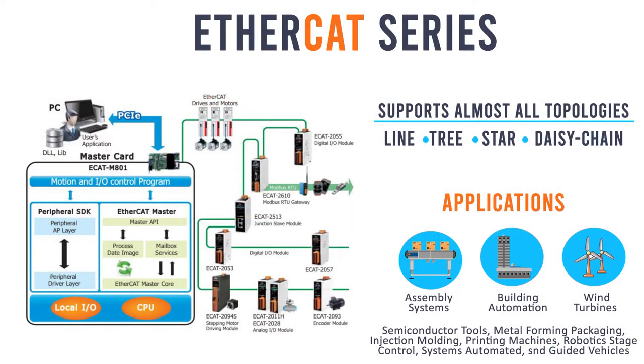Line, tree, star, or daisy chain — EtherCAT supports almost all topologies, and the combination of lines and branches is particularly beneficial. The connected ports can not only create branches but also directly integrate various IO modules, so no additional switches or active infrastructure components are required.